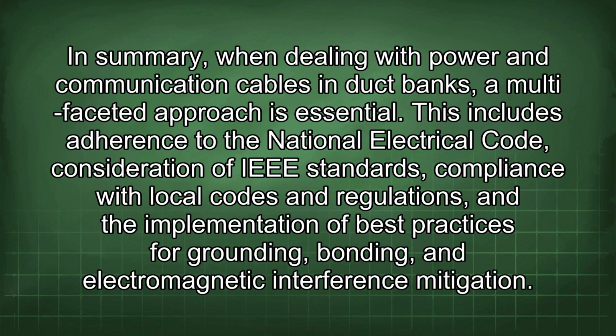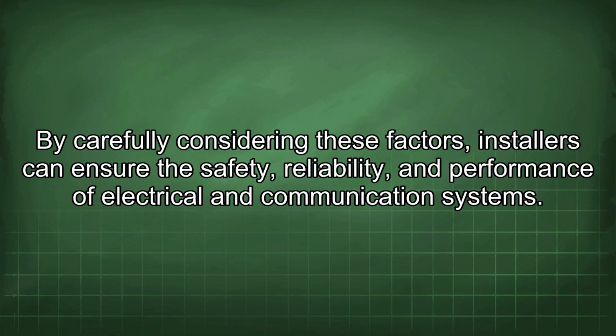In summary, when dealing with power and communication cables in duct banks, a multifaceted approach is essential. This includes adherence to the National Electrical Code, consideration of IEEE standards, compliance with local codes and regulations, and the implementation of best practices for grounding, bonding, and electromagnetic interference mitigation. By carefully considering these factors, installers can ensure the safety, reliability, and performance of electrical and communication systems.